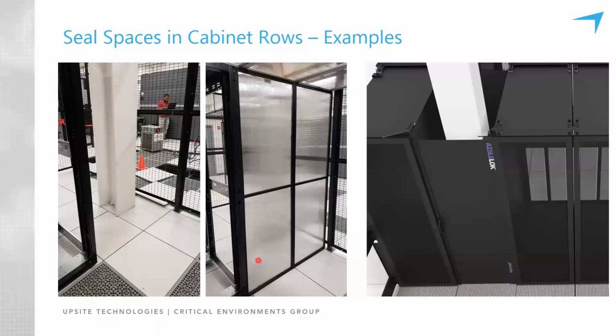On the right, this is an Upsite product. It's called a rack gap panel. It's a great product in that it can actually span these gaps, anything from kind of less than a foot up to almost 5 feet in width. So it's a universal product, used for the same application. It's an opaque product, so you've got options between doing something rigid and designed specifically for a particular cabinet height and aisle width, or something a lot more flexible and repurposable in these rack gap panels.